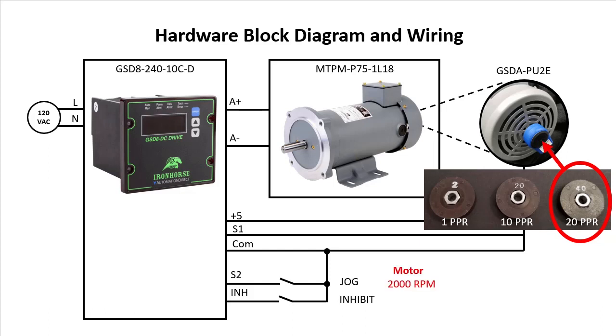My motor can only do 2000 RPM and the encoder has 20 pulses per revolution so that's a max pulse rate of 40,000 pulses per minute, which is way under the drive's max input pulse rate of 600,000 pulses per minute. Beware the smaller 5 amp drives can only do 50,000 pulses per minute, but it's still better than the 40,000 PPM we need so we are good no matter which drive we use.